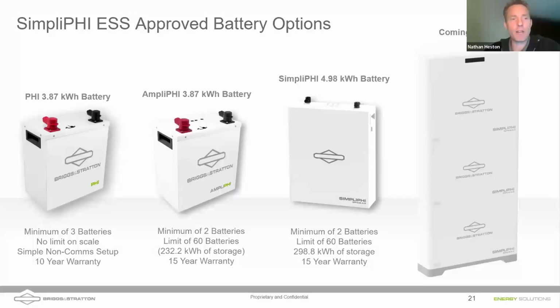But what we're looking at here on the left side of the screen is a Phi battery. That Phi battery is a non-communicating battery, so you don't have the advantages of the easy setup where the inverter auto-populates your settings. It also doesn't give you quite as much information, but the Sol-Ark has fairly good monitoring of these batteries, and sometimes less is more. These Phi batteries are very popular for big installs, and I'll show you some examples of those in a minute. The SimpliPhi battery is a very popular choice. It's got communications. It's an indoor rated battery, just like the Phi. You can't put it out in the rain. But it's got closed loop communications, and you can get a lot of detail, especially with our monitoring system, the Energy Track monitoring system, about individual batteries, their performance, if there are any issues, temperature, that kind of thing.